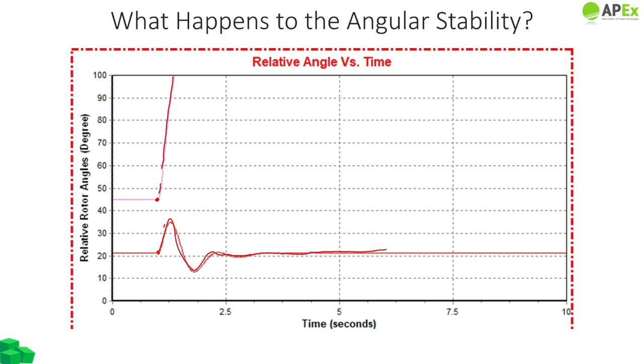Based on all three analyses, let's draw certain conclusions. For short transmission lines up to 50 miles, the thermal limit appears to be the binding limit. That is, the thermal limit would limit the capacity of a short transmission line. Among the medium transmission lines, which have lengths of 50 to 150 miles, voltage happens to be the binding limit, as in the transmission capacity is limited by voltage stability requirements. But for very long transmission lines that span over 150 miles, it is the angle stability considerations that limit the transmission capacity. So this concludes our discussion on transmission.